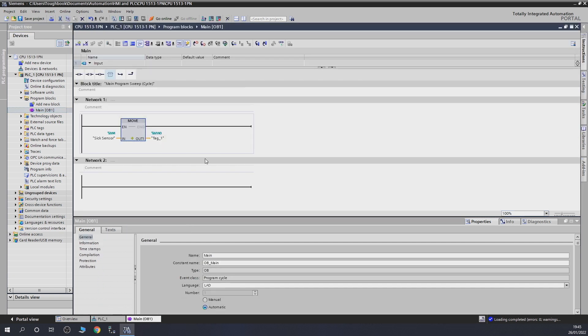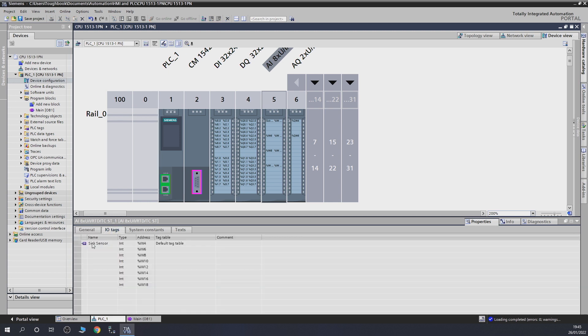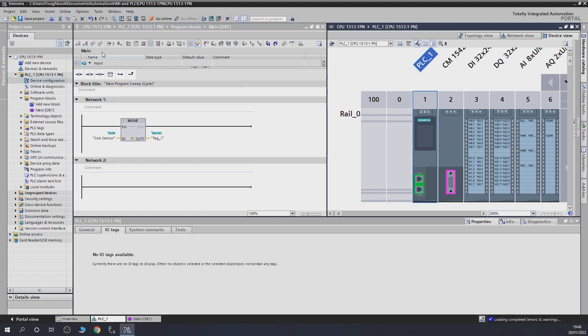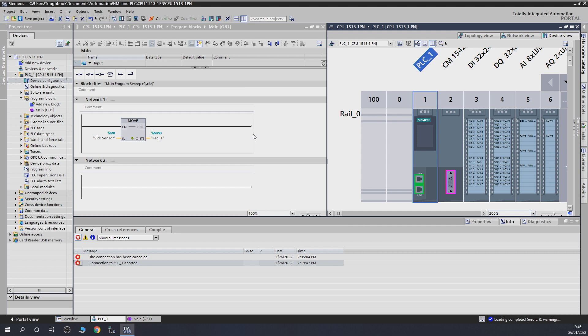All we're going to do now is use a move instruction I've already created. We're taking IW4 — which you can find in the configuration under IO tags, where all the channels are listed: IW4, 6, 8, 10, 12, 14, 16, and 18. You can name them as you wish. I find this the easiest way to tag them up. You go in, do a split screen, and drag the tag. We're moving data from IW4 into memory word zero. The channel is ready for testing — let's select our CPU and download the whole thing.